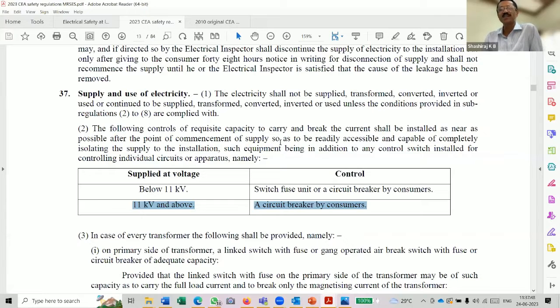Accommodating a circuit breaker by all 11 kV consumers. Earlier, as you rightly said, there was a distinction between voltage class and the connected load, and load also was a criteria before fixing the requirement of a breaker. But they have done away with that. And your other doubt, or question, was whether it is applicable to DISCOMs.